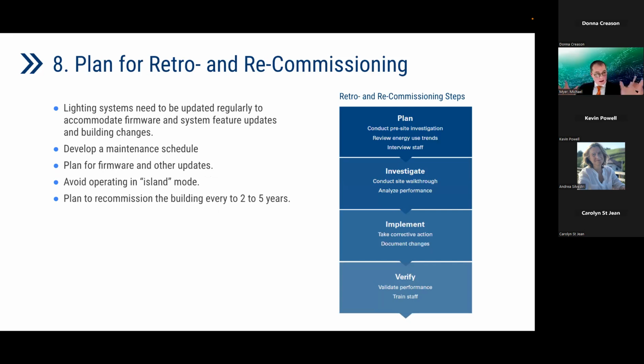That's the baseline commissioning. Then people come into the space, the building operates, and things change—spaces change, occupancy patterns change. The pandemic is a great example: pre-2020 everyone was in from 8 to 5, now you have a much more flexible workspace. That may affect how your occupancy sensors work, and other control systems too. Don't just assume nothing changed.